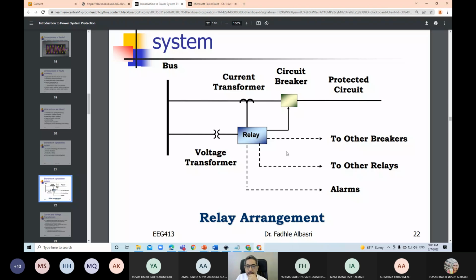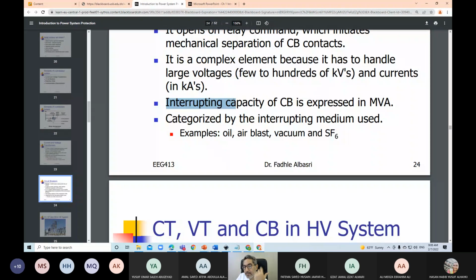Normally, the interrupting capacity of a circuit breaker is expressed nowadays in kiloamperes. It's not in MVA now. MVA was a previous practice, but nowadays we call it the interrupting capacity of a circuit breaker, in kiloamperes.